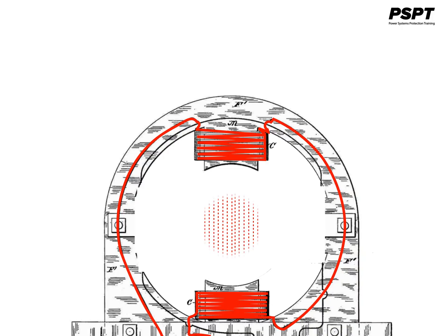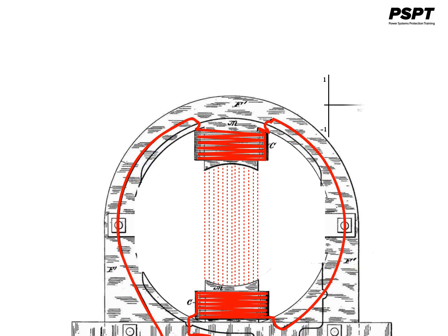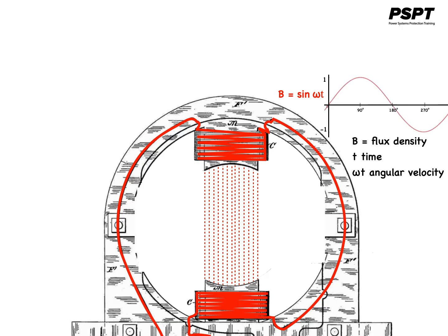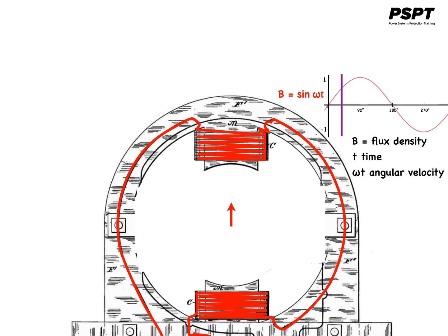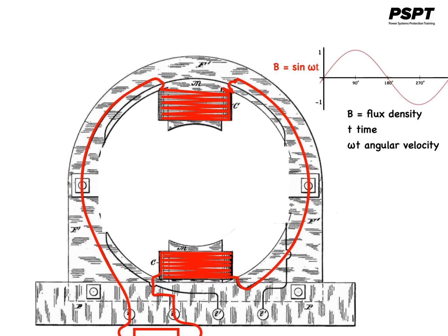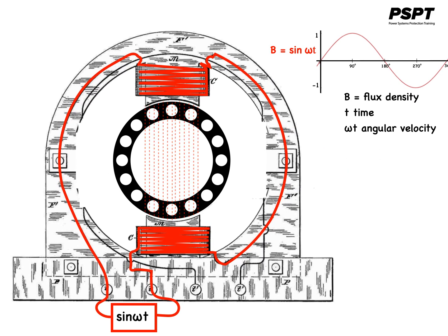The single-phase stator winding produces a magnetic field that pulsates in strength in a sinusoidal manner. The field polarity reverses after each half cycle, but the field does not rotate. Consequently, the alternating flux cannot produce rotation in the stationary squirrel cage rotor. This fact is easy to see from the examination of the motor when it's in its stationary position.